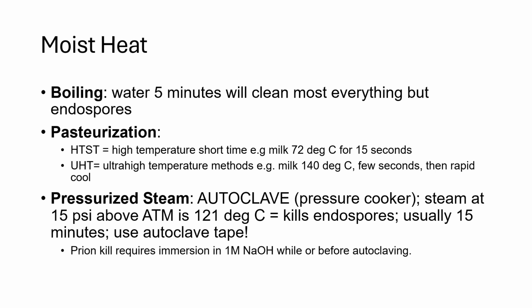Autoclave tape is something that is standard in near any autoclave. It's a tape that has colored stripes on it that you can't see until it experiences 121 degrees for about 15 minutes, and then it'll become striped black. So it'll go from white to striped, and then you know that the tape in the autoclave experienced the proper conditions. Because a piece of sterile glassware goes in clean, it comes out looking the same. So unless you have some control to know that it was sterilized, that's what the autoclave tape is for. And I'll show you guys this in the lab.